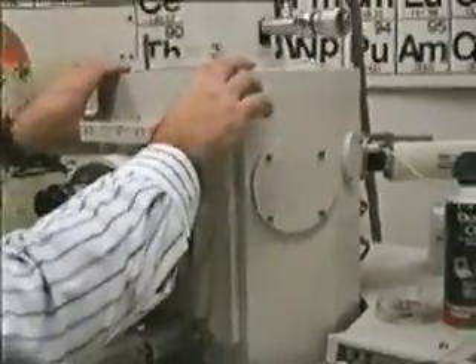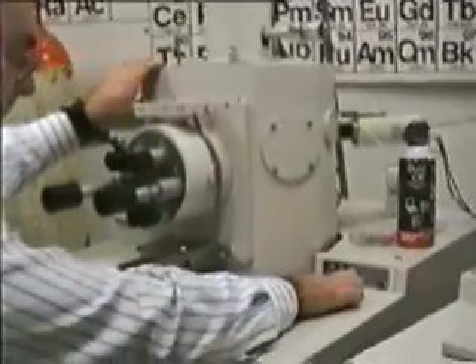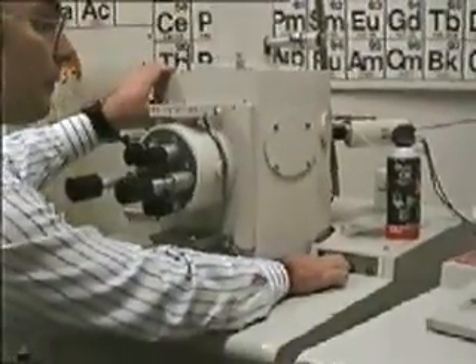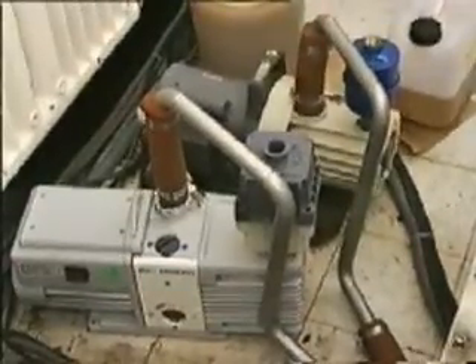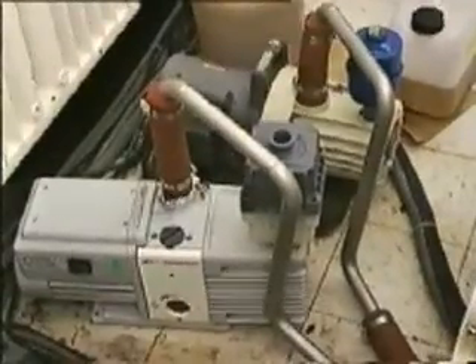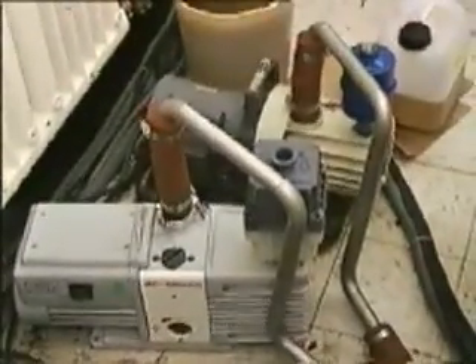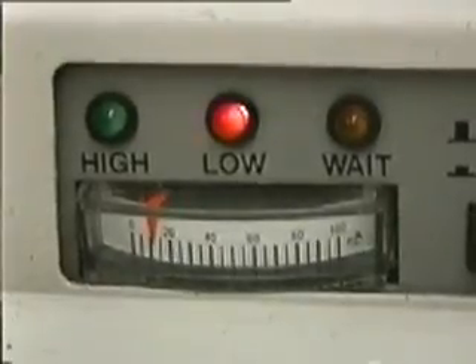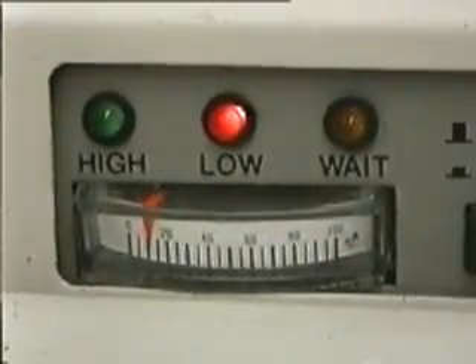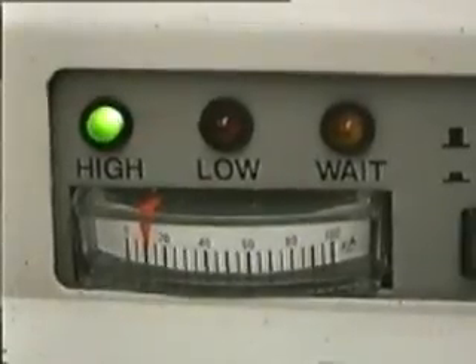By pressing a button, the operator activates a mechanical pumping system that evacuates air from the specimen chamber and the column of the scanning electron microscope. The pumps are located behind the microscope console.